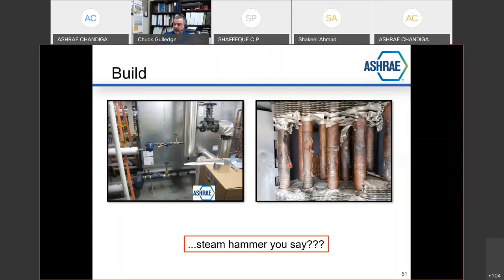the condensate collects, and on 100% outside air, you're actually going 100% steam, and you're modulating the space and bypass dampers for control. It's not really a soft start scenario. That will water hammer, and the shock wave will destroy a steam coil. All right, let's move on.